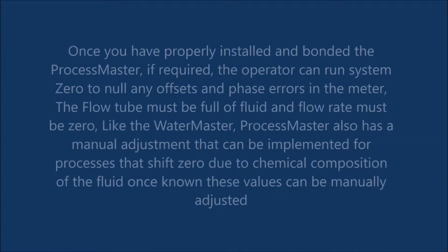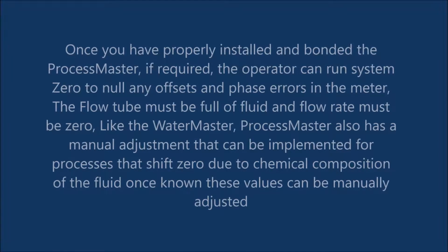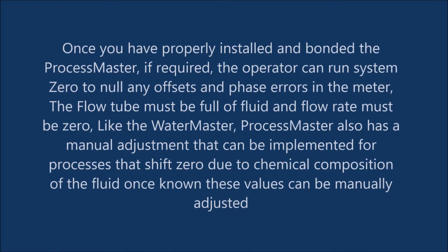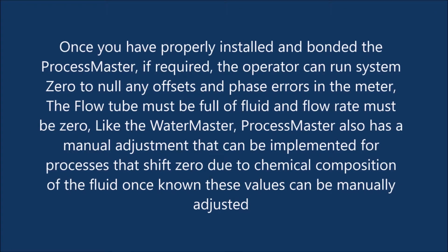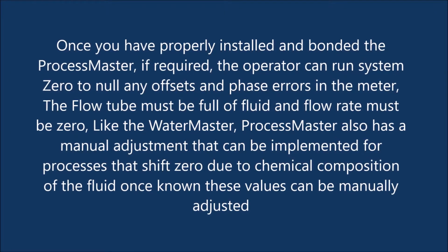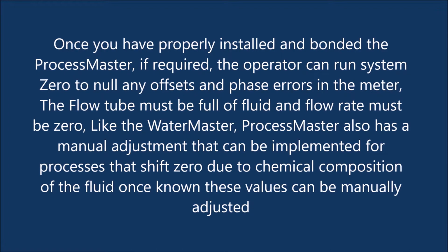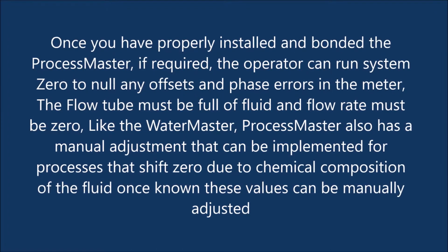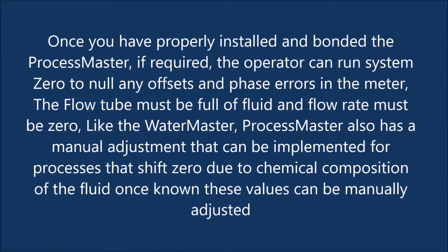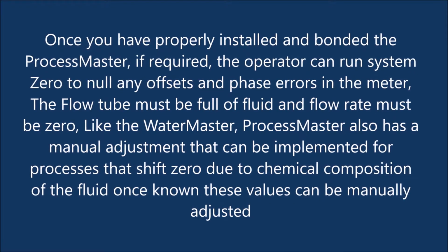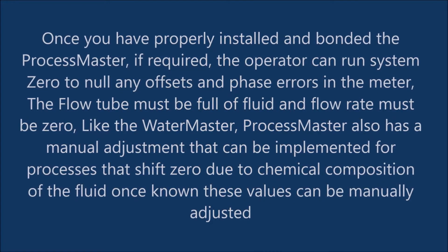Processmaster, System 0. Once you have properly installed and bonded the Processmaster, if required, the operator can run System 0 to null any offsets and phase errors in the meter. The flow tube must be full of fluid and flow rate must be 0, like the WaterMaster. Processmaster also has a manual adjustment that can be implemented for processes that shift 0 due to chemical composition of the fluid. Once known, these values can be manually adjusted.